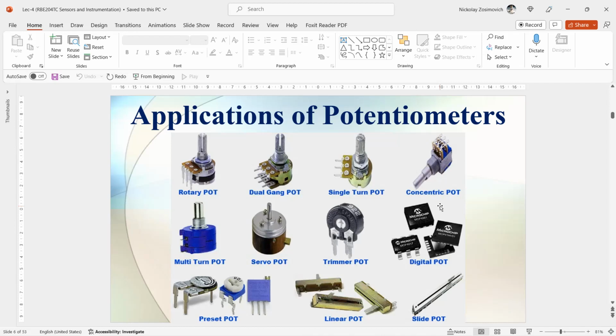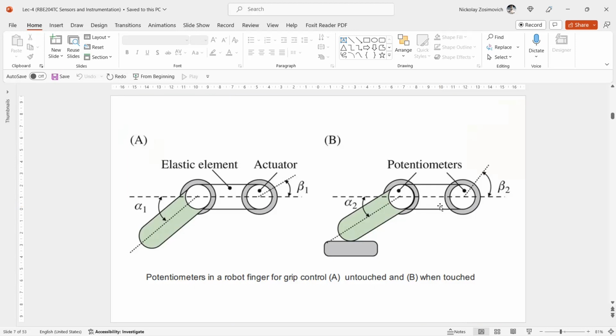However, this might introduce additional backlash and friction, which reduces the accuracy of measurement. But proper alignment of object and sensor is extremely important here. So, potentiometers are widely used in all kinds of mechatronic systems to obtain information about angular position of rotating parts. When small dimensions should be combined with a high resolution, potentiometers may be preferred over the popular optical encoder. For example, controlling a multi-fingered robotic hand requires several angular position sensors located at the joints of the fingers. Right? Right. Potentiometers have been considered as one of the possibilities to achieve this goal.